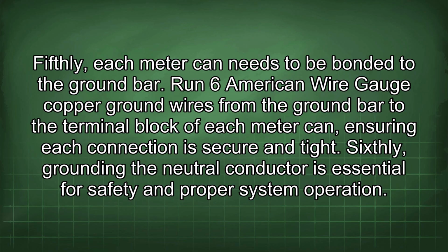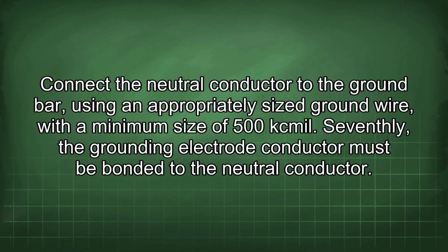Fifthly, each meter can needs to be bonded to the ground bar. Run 6 American wire gauge copper ground wires from the ground bar to the terminal block of each meter can, ensuring each connection is secure and tight. Sixthly, grounding the neutral conductor is essential for safety and proper system operation. Connect the neutral conductor to the ground bar using an appropriately sized ground wire with a minimum size of 500 kcmil.